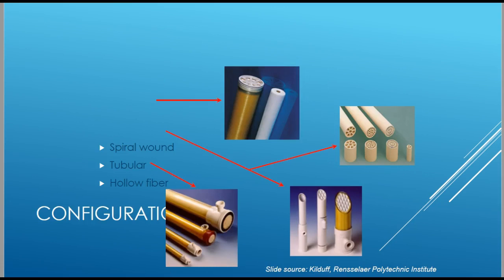Here are typical configurations of membranes. They originally were flat sheets and were configured as spiral wound membranes to compact the area of flat membranes. There are tubular membranes that are round and arranged like conventional heat exchangers, and there are hollow fiber type membranes that take advantage of a very high surface area.